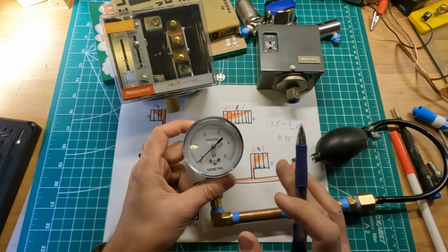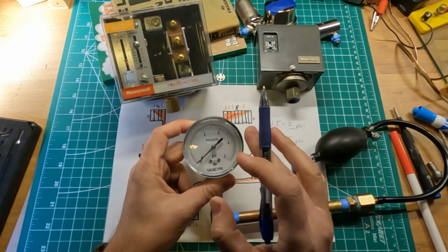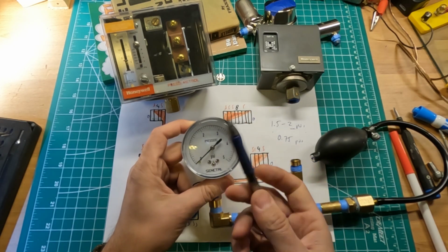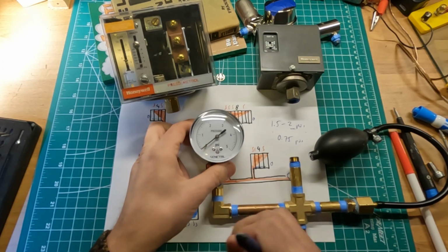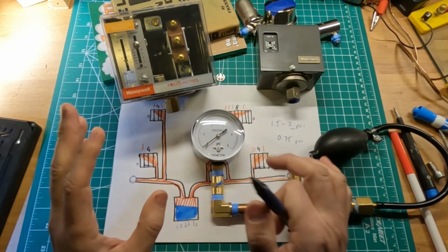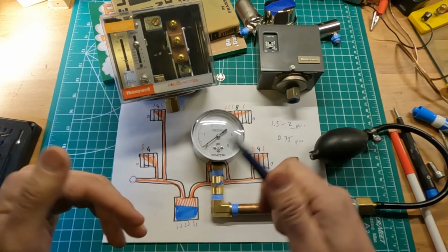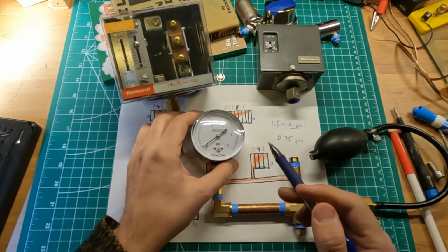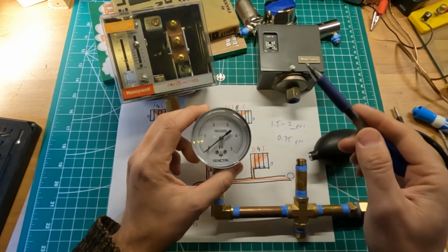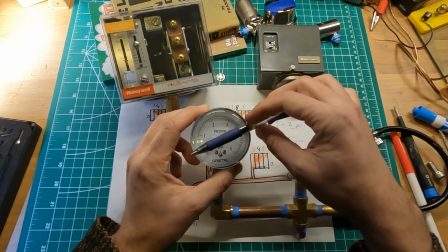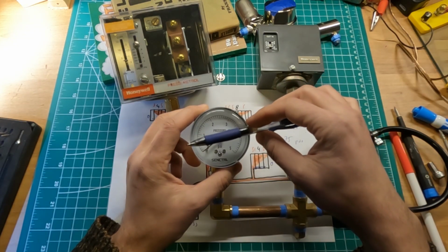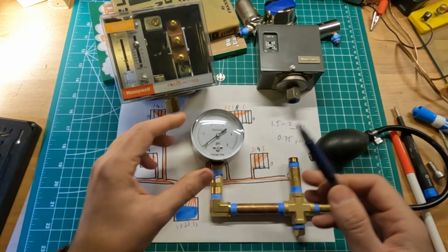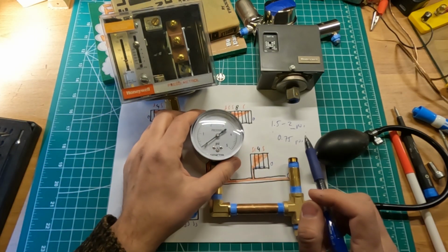And in theory, if all of the things are working properly, it will shut down the boiler. But remember, all of that 0 to 1.5 psi is basically wasted steam, or rather, wasted energy that it took to warm up this steam. So in theory, you should shut down the boiler the moment the gauge starts seeing some pressure, so that you don't waste your steam unnecessarily warming up the water.